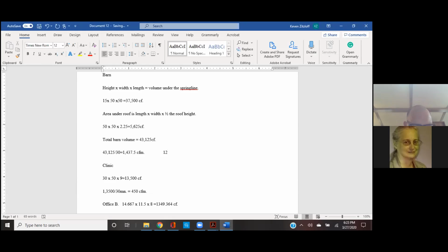For the barn, yeah. Doesn't it make sense to have them kind of bigger and dumping? Yes. I would rather have it bigger. It'll save you on duct work and all that kind of stuff. Okay. And so you would say 1,000 cubic feet per minute per duct outlet?